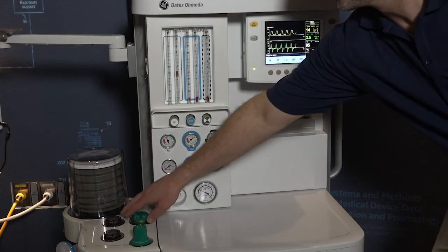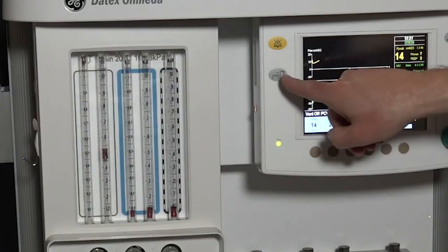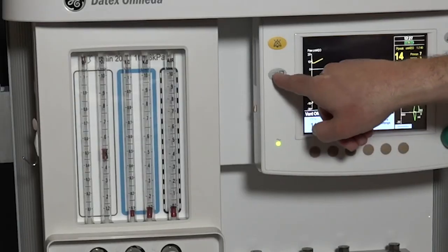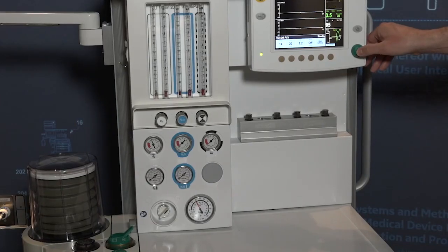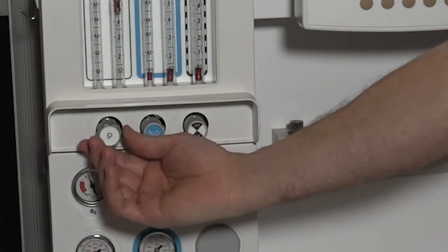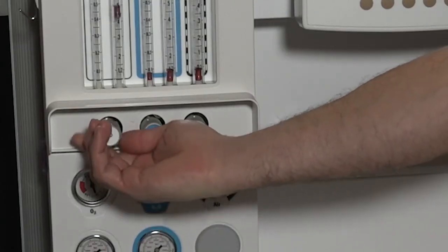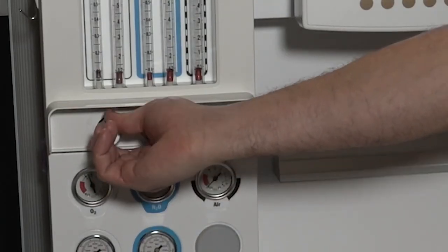Set the bag to vent switch to bag. Press the end case key. Press the ComWheel to confirm. Turn off the oxygen and air gas flows.